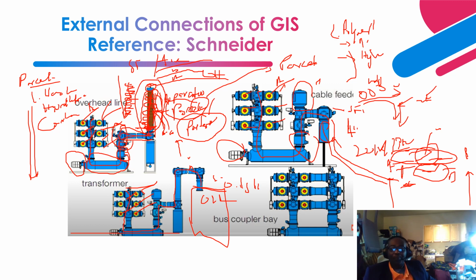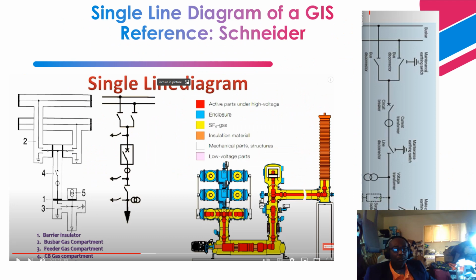Once we close the tiebreaker or the bus coupler, then only one source comes into play. Right? Okay, so that is also another external connection that we can have where the tiebreaker can be fed from here. Right? We have a feeder that comes in here and basically feeds these two buses. Next, let's go through a single line diagram of a gas insulated switchgear.